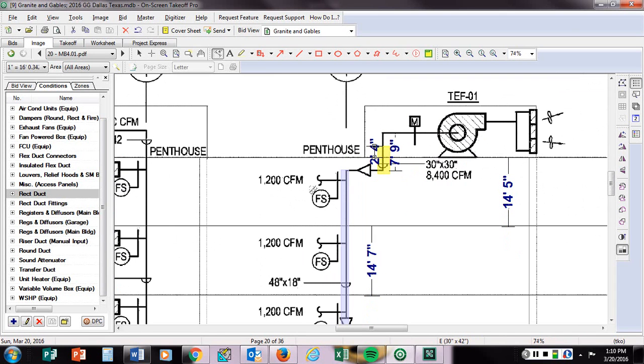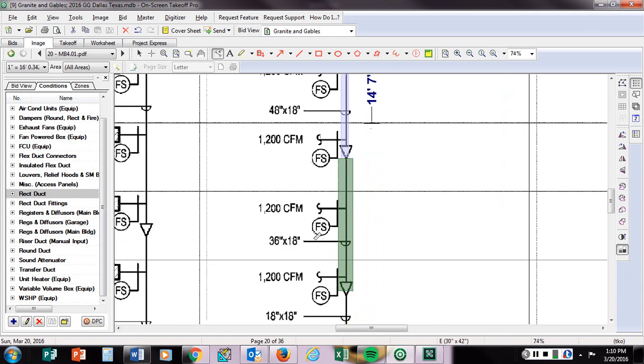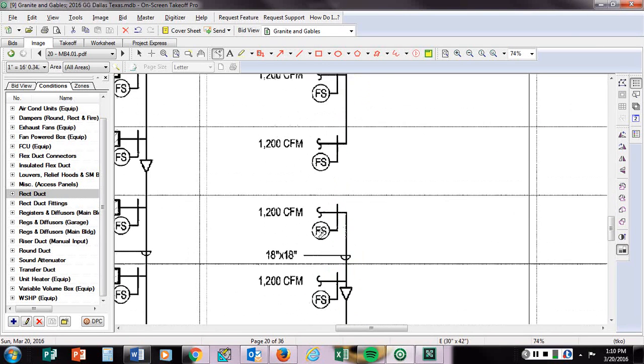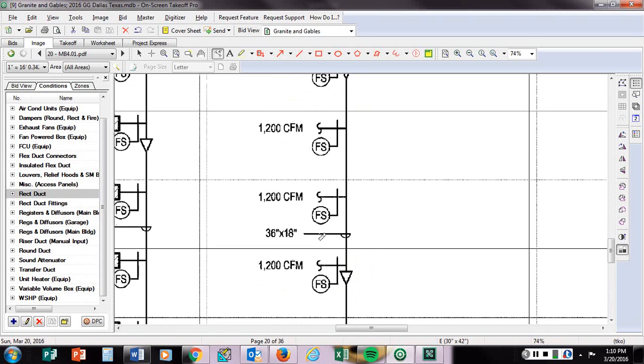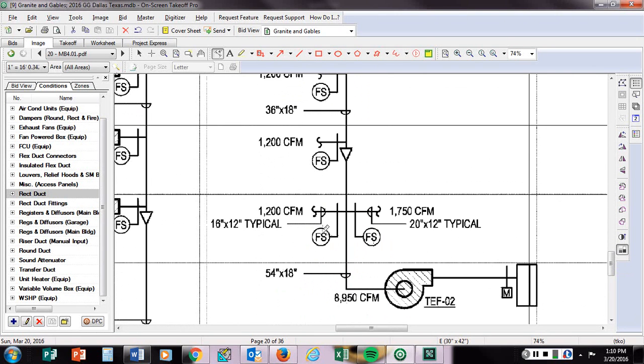You'll see we've got a fire and smoke damper, and we've got 1200 CFM going to every floor. I think other than 7 has got that extra bathroom in it. So by the time we get to 7, this is it right here where it's got 1200 plus another 1750 on there. You can see there's 2 fire and smoke dampers there. And then there's this exhaust fan too that goes down here.